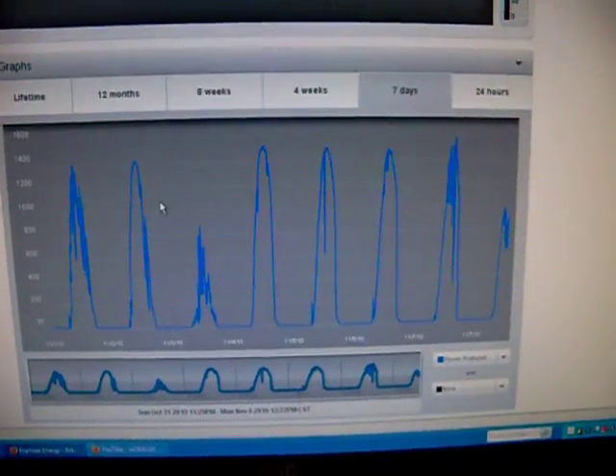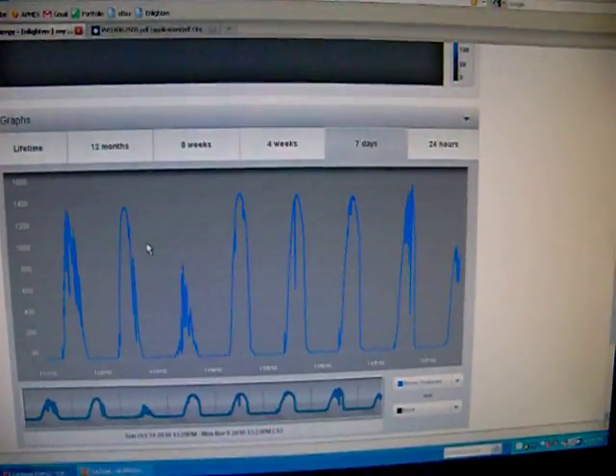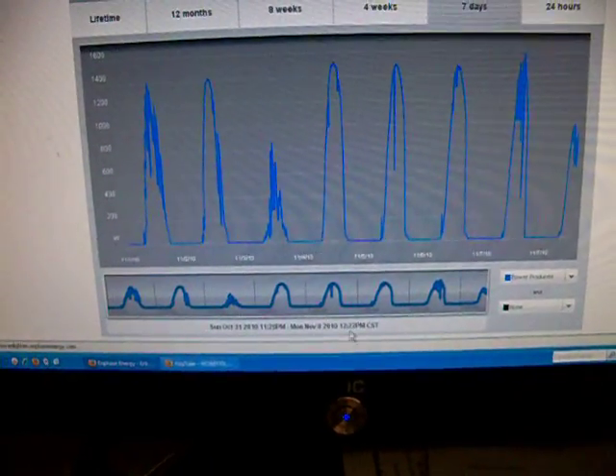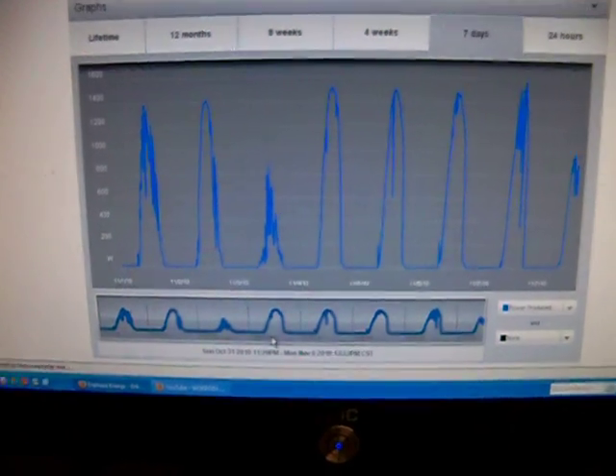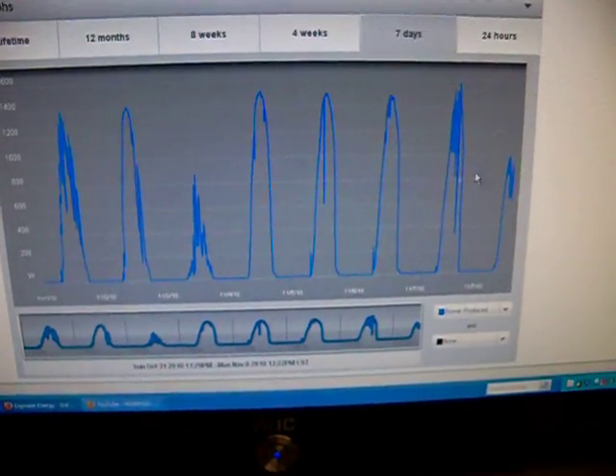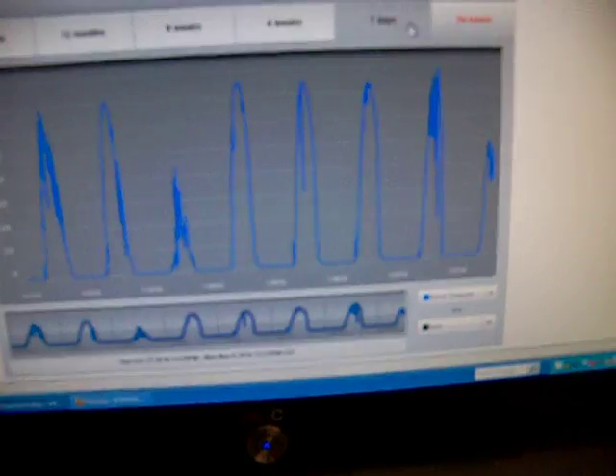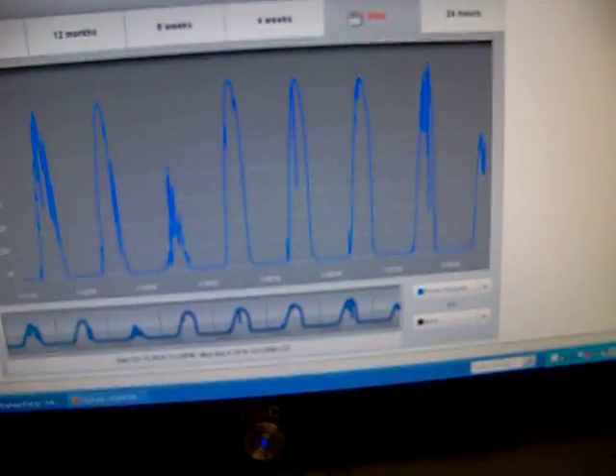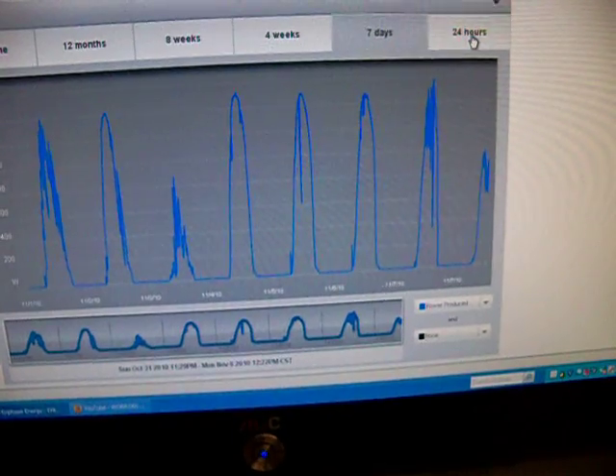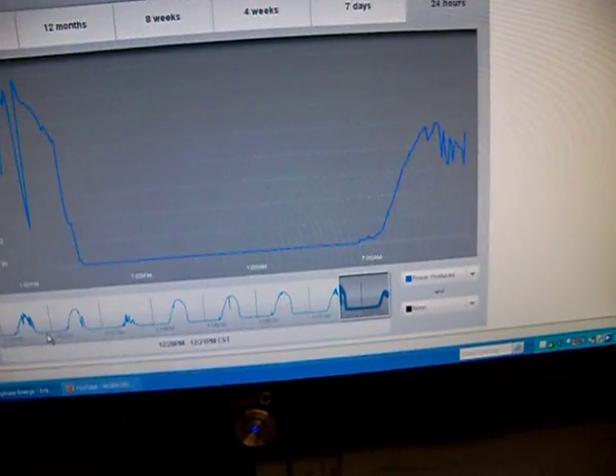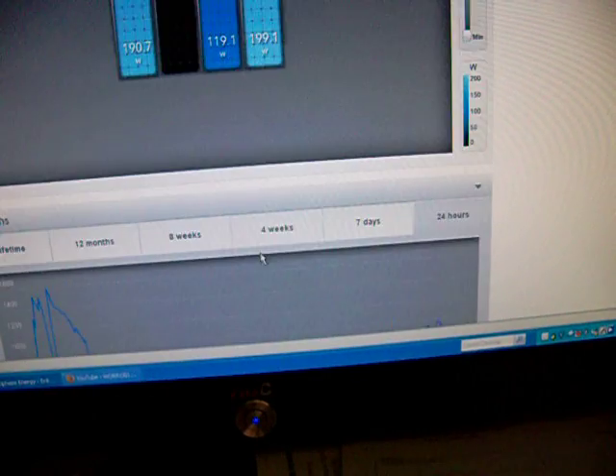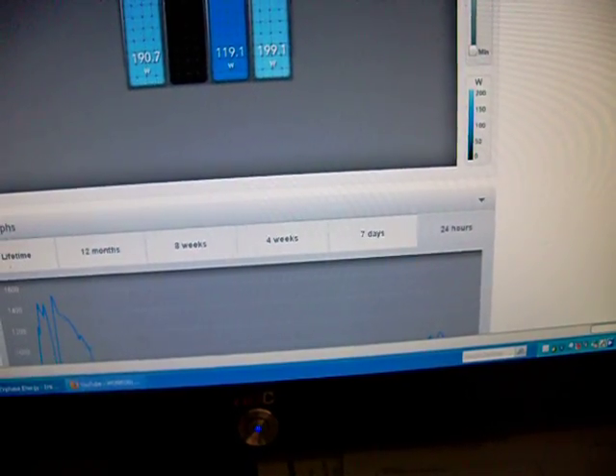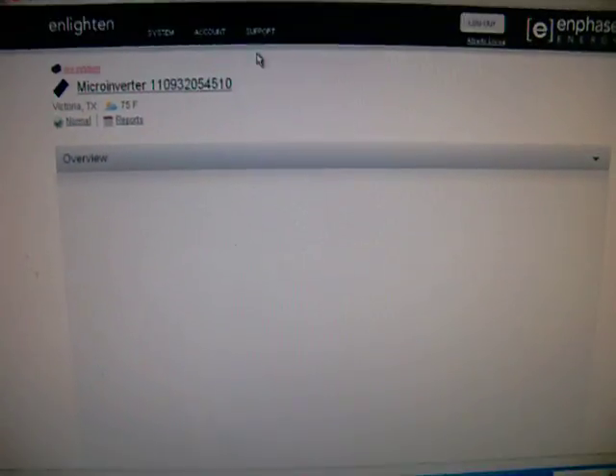Now these are polycrystalline panels. But for the most part, they're doing very well with those microinverters. The one nice thing about the Enphase inverters is that you can monitor them like this. You can look at going back at a lifetime of four weeks, 24 hours, and then the day-by-day for each one. I can actually zoom in on any one panel and take a look at it.